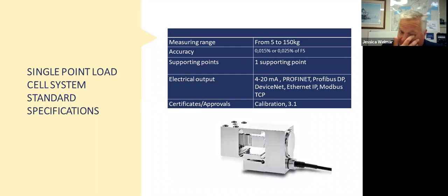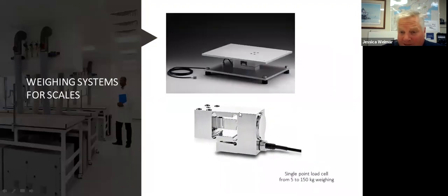This is a little bit of a different animal. This is called a single point load cell, and this is used in scale applications. Lower capacities, between 5 and 150 kilograms, higher accuracies. But the real interesting part about this cell is it's designed with a more robust body to be able to accept off-centered loads. So this is the typical installation where you'd have that in the middle. You could offset loads to any one of these corners, and this would remain accurate, where other styles wouldn't be able to handle that degree of offset. So these are designed specifically for scales.